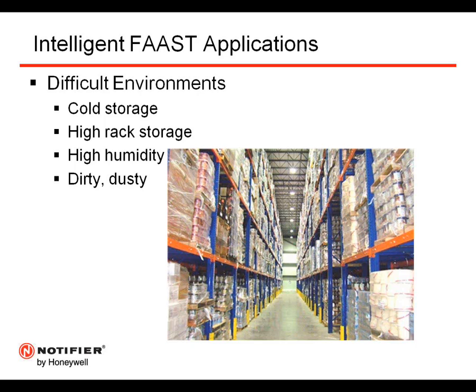Another thing about high rack storage or just high ceiling areas in general is the effects of stratification on smoke. As smoke starts to rise and rise and rise, eventually it's going to get to a level where it's going to start to cool off and it's going to continue to rise no longer. So if you have a high ceiling area and you had conventional or even addressable spot detectors on that ceiling, that smoke might never make it to that chamber. So another application for Intelligent FAAST.